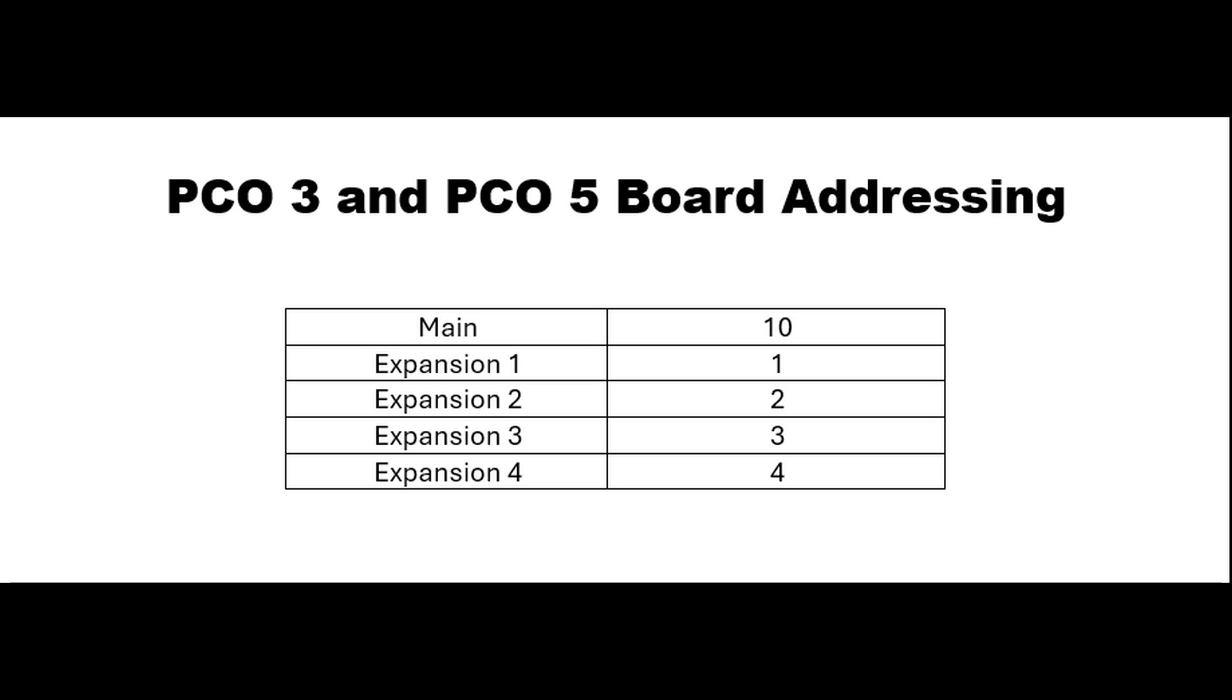Now you will need to determine the correct address for the replacement controller using this chart. Main boards are address 10 and expansions are addresses that match their number in the system. For example, expansion 1 is address 1.